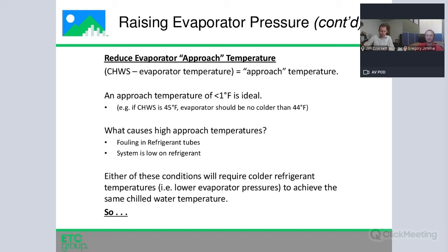This is an issue in a surprising number of chillers. Look at your chillers. A lot of times your chiller display panel will tell you what the refrigerant temperature is. Compare that to the chilled water temperature. If there's a large delta between those two, by more than a degree or two, something's not right with your system. You may need to add some refrigerant. You may need to clean the chiller tubes, but something is not right.